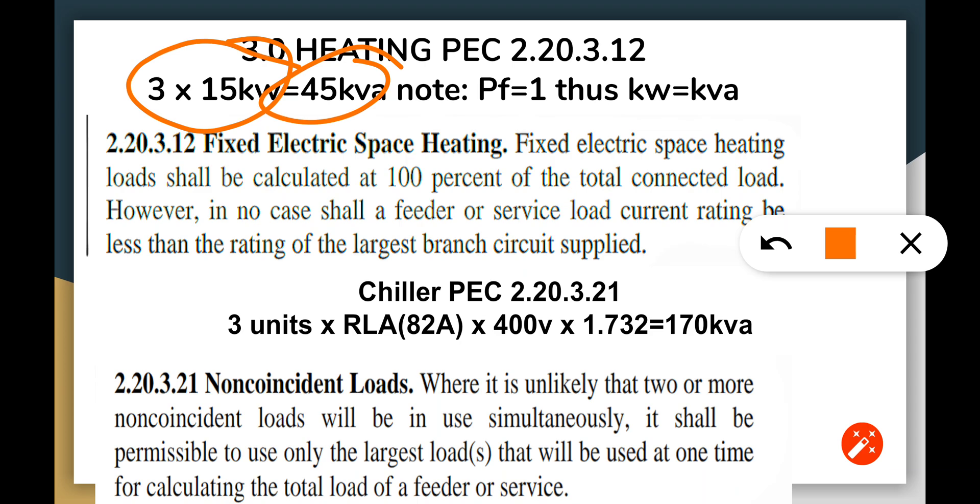We have the chillers here. We have two units of chillers with rated load amperes of 82 amperes times three phase 400 volts times 1.73, so you should get 175 kVA. These are non-coincident loads because they are not activating at the same time. When the heating is provided there's no chiller, when cooling is provided there's no heating. That's what we call non-coincidental loads.